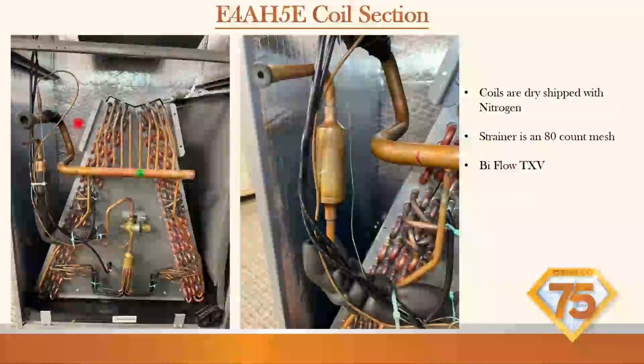Strainer, and these things do get plugged up easy, so make sure you are bleeding nitrogen during brazing, because if you're not eliminating that oxygen in the copper lines when you hit it with the torch, you're going to oxidize that copper. As soon as you release that refrigerant in it, it's going to clean that copper and push all the oxidation ash into the strainer, causing issues.